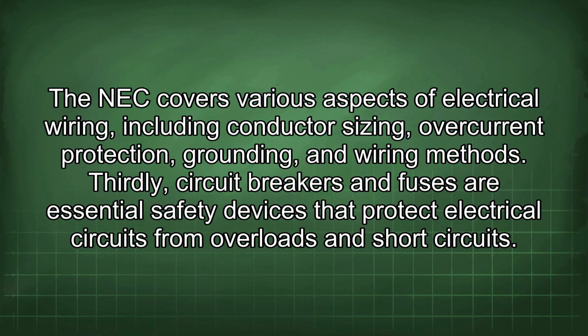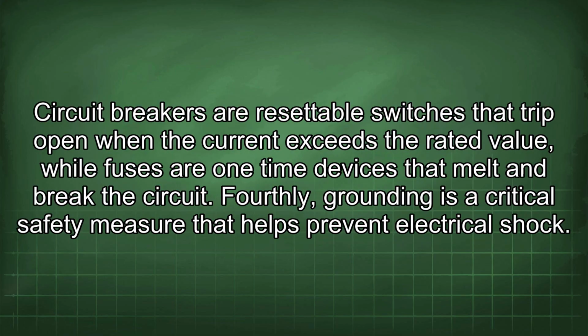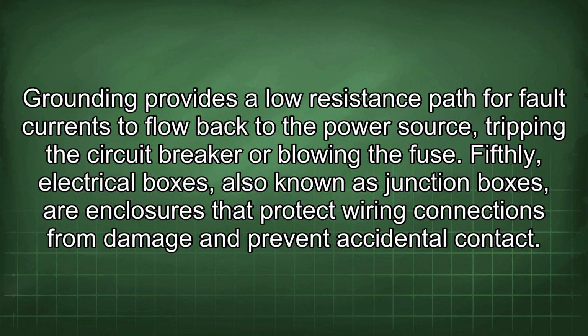Thirdly, circuit breakers and fuses are essential safety devices that protect electrical circuits from overloads and short circuits. Circuit breakers are resettable switches that trip open when the current exceeds the rated value, while fuses are one-time devices that melt and break the circuit. Fourthly, grounding is a critical safety measure that helps prevent electrical shock. Grounding provides a low-resistance path for fault currents to flow back to the power source, tripping the circuit breaker or blowing the fuse. Fifthly, electrical boxes, also known as junction boxes, are enclosures that protect wiring connections from damage and prevent accidental contact.